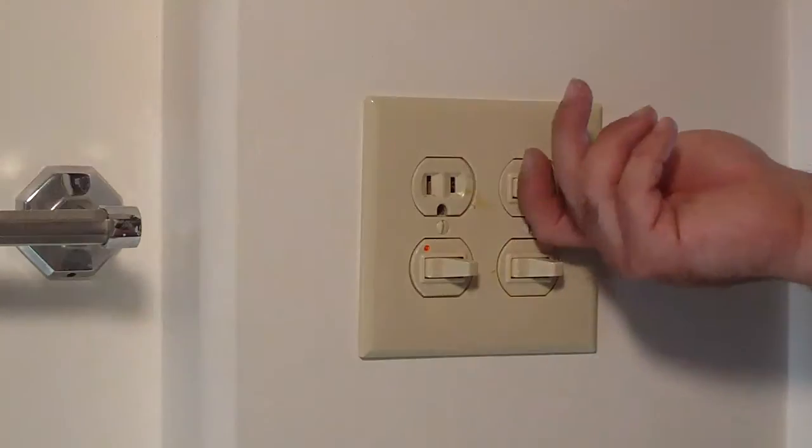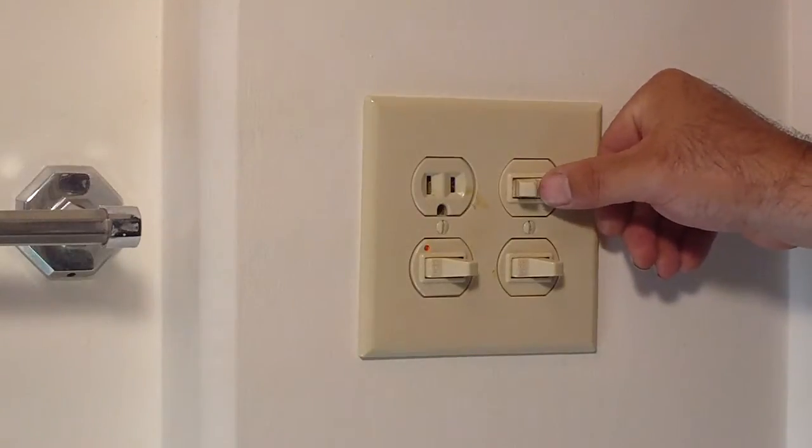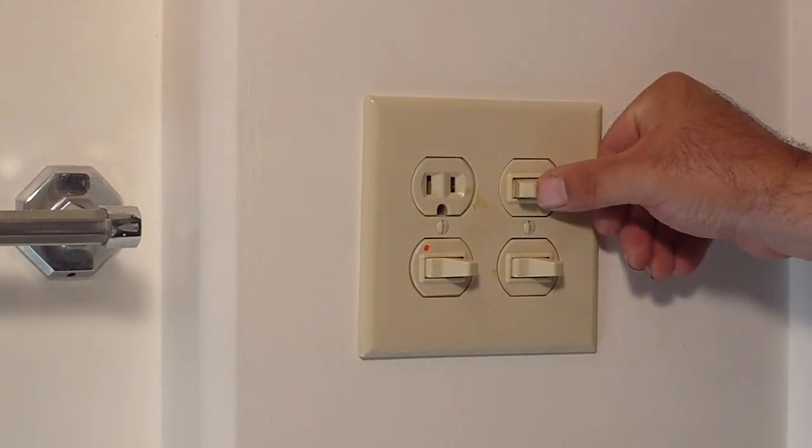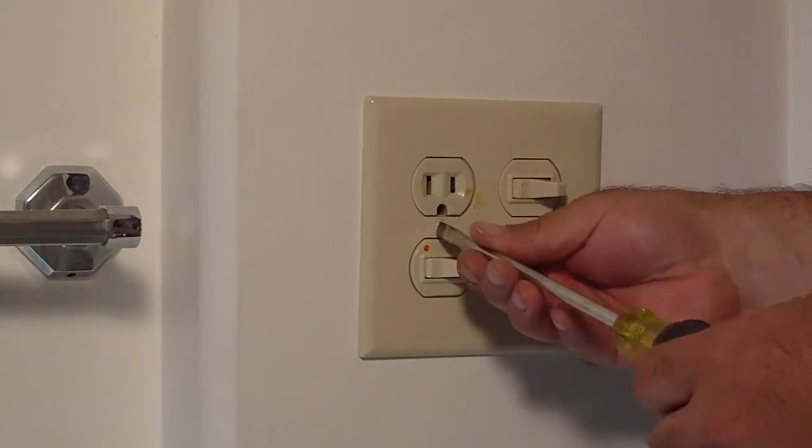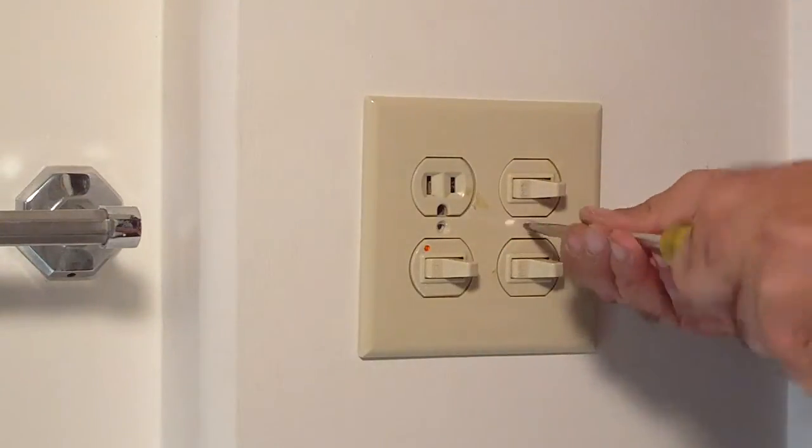Overhead light. And you might say, well, it's working. Yeah, it is. But when you get moisture, or sometimes I'm barely touching that switch there and the light, fluorescent light flickering, and you can hear it buzzing. That's not good for the ballast at all. And I changed this once before, probably about 10 or 12 years ago.